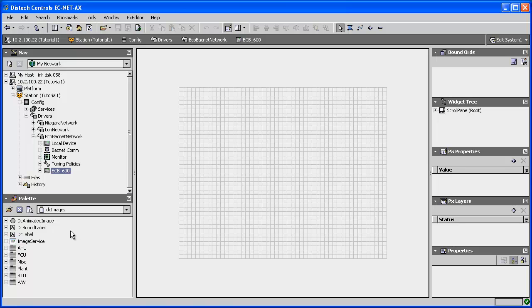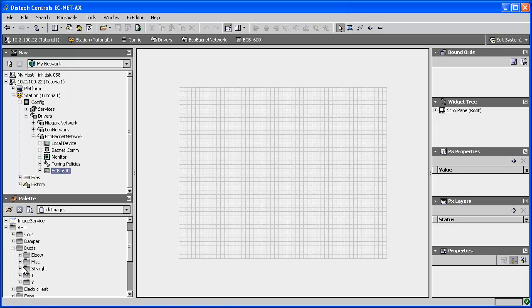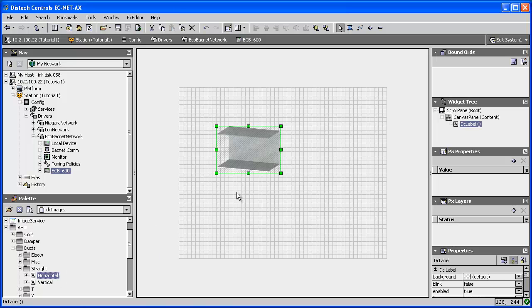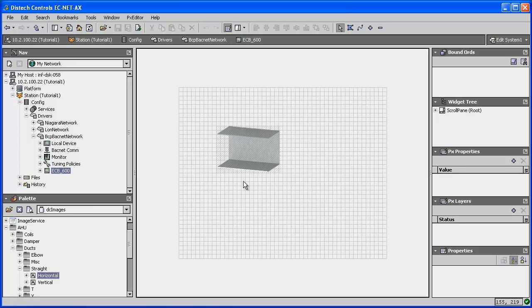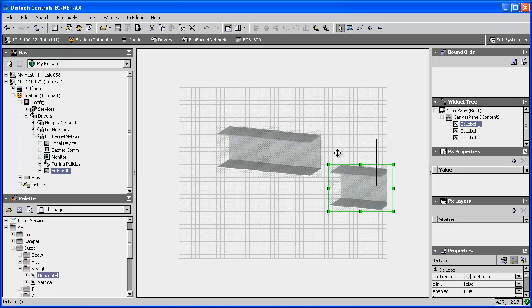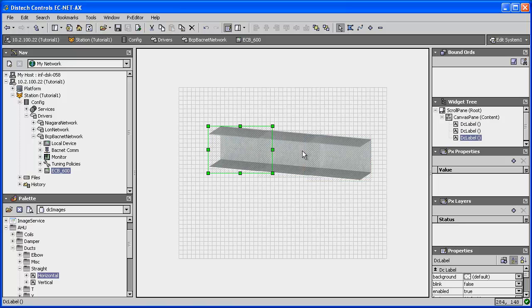First, make sure that your DC Images palette is selected — this is where you'll select the objects you wish to add to your graphic. I will add a horizontal duct, locate it, and then drag and drop it onto the graphics page. If for some reason the graphic comes out unclear, simply click the Toggle Edit Mode icon at the top to refresh the image. I will now add a few more straight ducts and align them to obtain a wider duct. You can move these graphic images around until you've obtained your desired result. These images are referred to as graphic labels — inanimate graphical widgets such as a duct or a plenum that are not linked to any value.